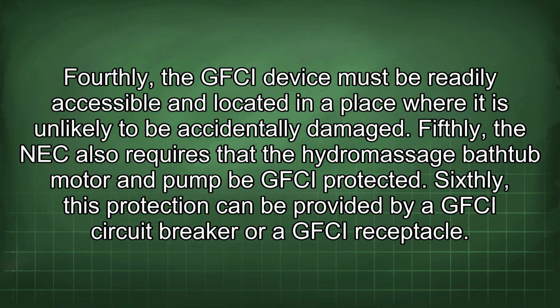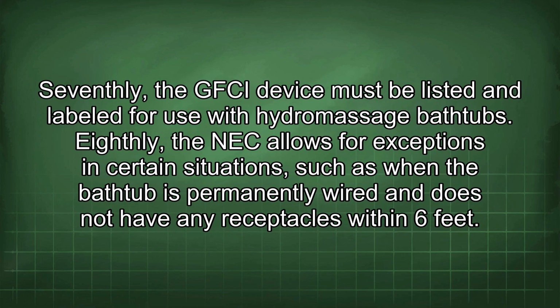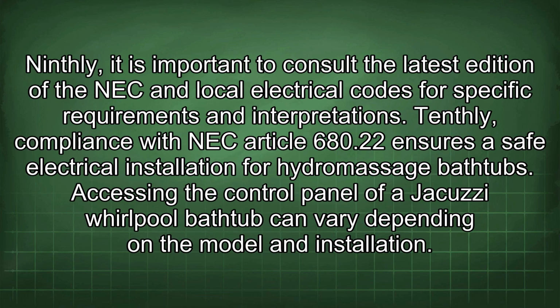Sixthly, this protection can be provided by a GFCI circuit breaker or a GFCI receptacle. Seventhly, the GFCI device must be listed and labeled for use with hydromassage bathtubs. Eighthly, the NEC allows for exceptions in certain situations, such as when the bathtub is permanently wired and does not have any receptacles within 6 feet. Ninthly, it is important to consult the latest edition of the NEC and local electrical codes for specific requirements and interpretations. Tenthly, compliance with NEC Article 680.22 ensures a safe electrical installation for hydromassage bathtubs.